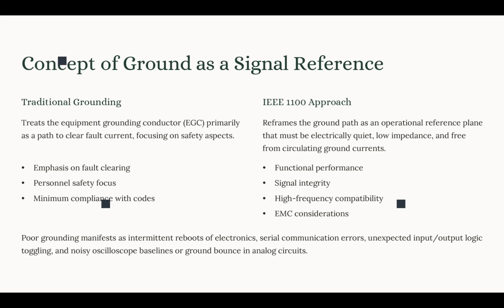So we already covered some of the design principles, like low impedance grounding. For power frequency, we have to limit our impedance to less than 1 ohm. And when we talk about the high frequency aspect of the ground impedance, the limit becomes 1 milliohm. So power frequency 1 ohm, high frequency 1 milliohm.